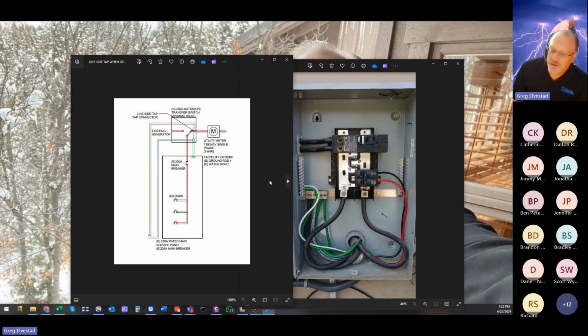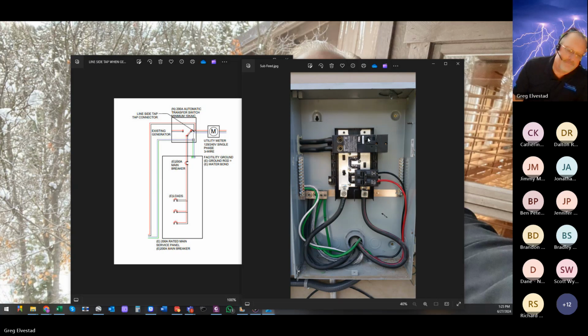Again, a supply tap. Transfer switches, another hot button. If you work in California, specifically if you work in Northern California at all, chances are very good that you may have seen someone cut in a transfer switch into a panel like the one on the right. What they do is they intercept these feeders, run them over to a transfer switch, then come back into the breaker and then go on to feed the thing. Again, a violation of the listing of the panel. Creative, and it does work, but it's wrong. So we can talk about that if you'd like, as far as what to do when you encounter that.